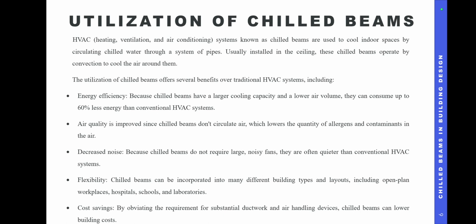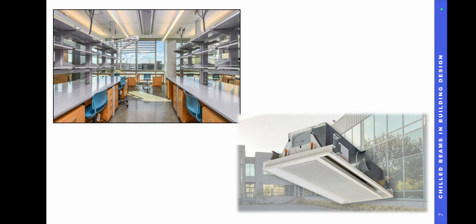Air quality is improved since chilled beams don't circulate air, which lowers the quantity of allergens and contaminants in the air. Decreased noise: because chilled beams do not require large noisy fans, they are often quieter than conventional HVAC systems. Flexibility: chilled beams can be incorporated into many different building types and layouts, including open plan workplaces, hospitals, schools, and laboratories. Cost saving: by minimizing the requirement for substantial ductwork and air handling devices, chilled beams can lower building costs. You can go through the benefits of chilled beams.